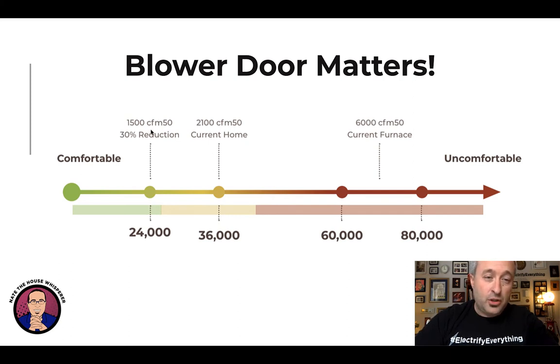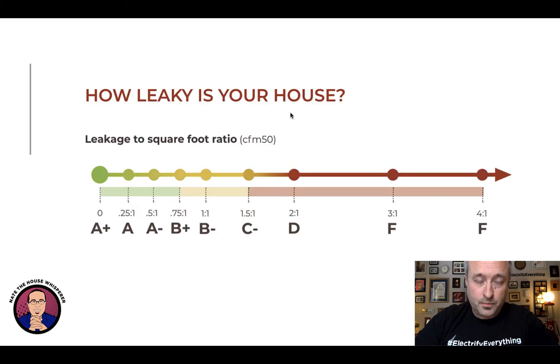You can see just by manipulating the blower door, the windows are the same, the insulation values are the same. We can be anywhere from a 2-ton heat pump up to a 70,000 BTU furnace, and we see leakage rates that high. Like, that happens. We've had several in the 5,000 to 6,000 range of tests this week, so that's not an out of line number on houses that are between 1,600 and 2,100 square feet. So this can happen. You need to know what the blower door is, or you're really guessing.